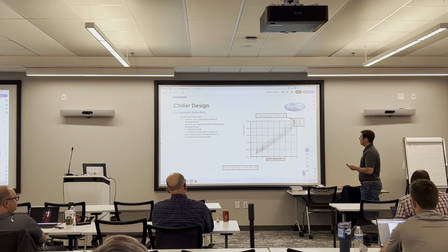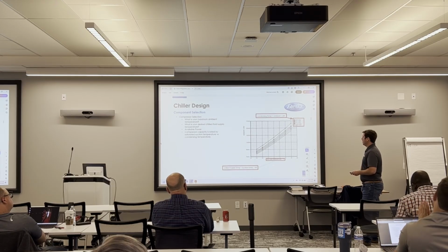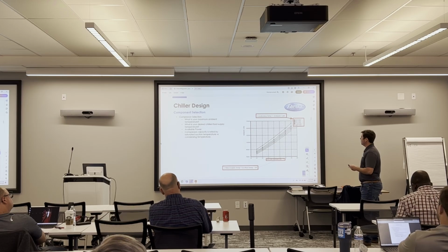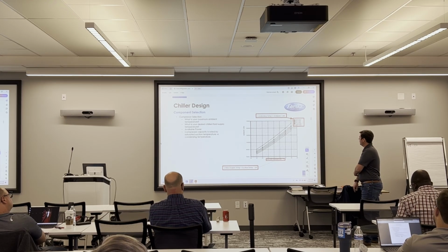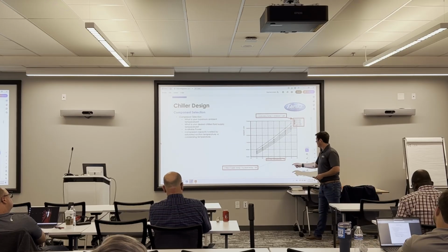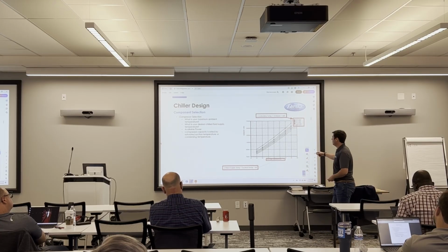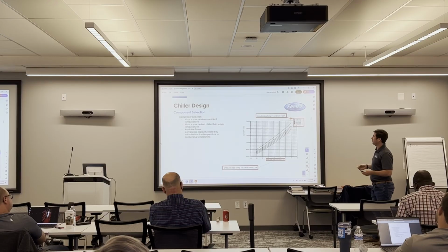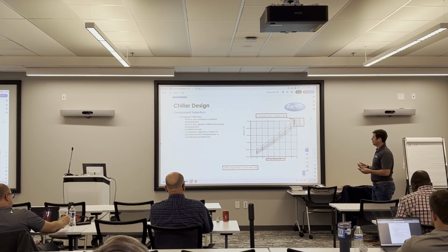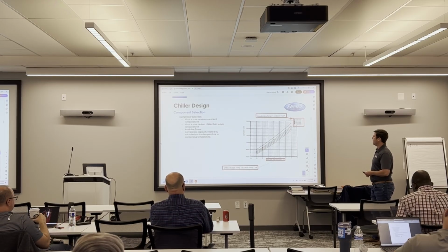So we have a curve here of capacity on the left-hand side. Down below we have our suction temperature, and these lines represent different ambient temperatures. Looking at this curve, you can see that as you increase your suction temperature or your chilled fluid supply temperature, you're increasing your capacity. And the same thing with ambient temperature. As you drop your ambient, you're dropping your condensing temperature, so you're gaining more capacity in that sense as well.